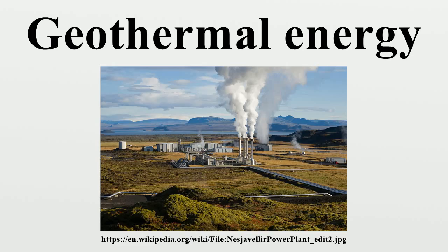The Wairakei power station has been running much longer, with its first unit commissioned in November 1958, and it attained its peak generation of 173 megawatts in 1965, but already the supply of high-pressure steam was faltering. In 1982, it was derated to intermediate pressure, with the station managing 157 megawatts. Around the start of the 21st century it was managing about 150 megawatts. Then in 2005, 8 megawatt isopentane systems were added, boosting the station's output by about 14 megawatts.